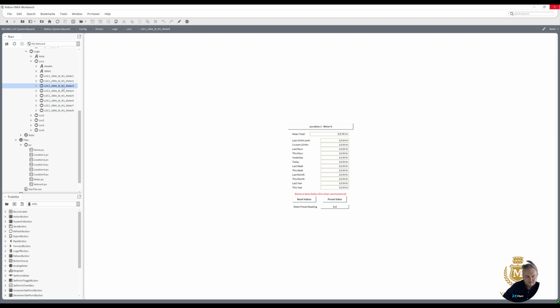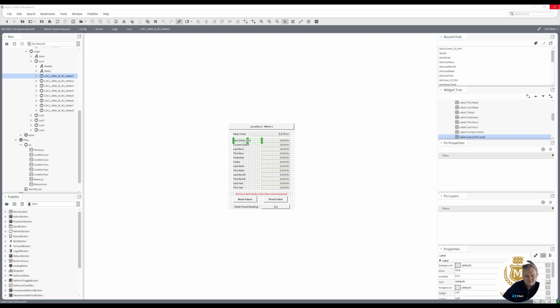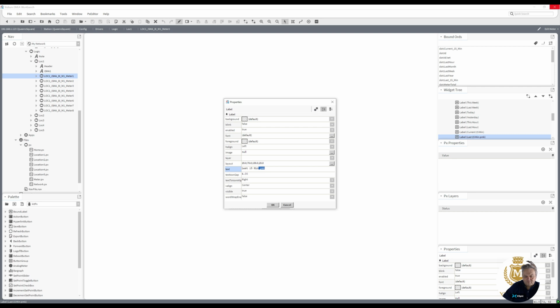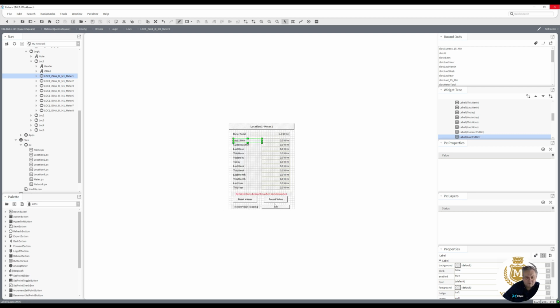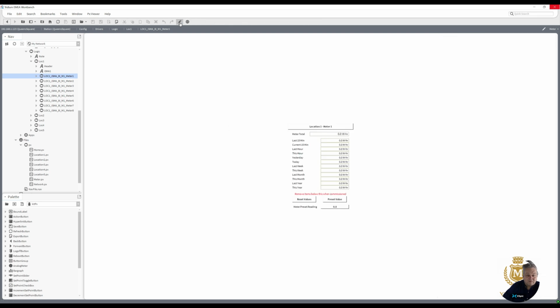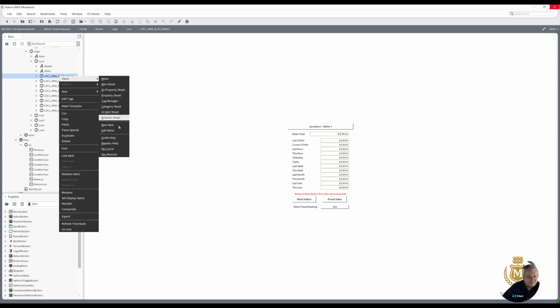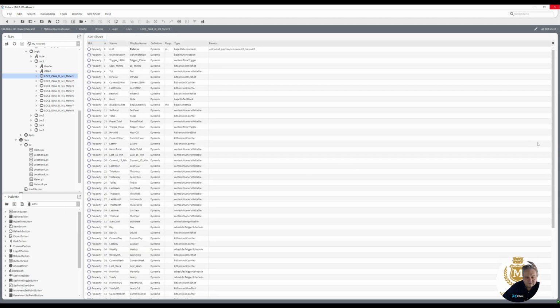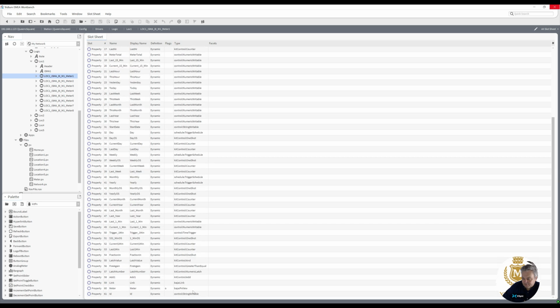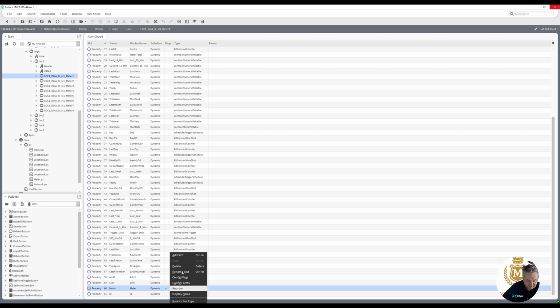Okay, it's the same graphic for all the meters, and I'll show you how I did that, because you do exactly the same for when you're doing fan coils. You won't make one graphic per fan coil. You will make one graphic for all the fan coils or all the fan coil types. So let's just right click that, views and AX slot sheet. Let's take out the view for that, which is this here. See this meter PX view? I'm just going to delete that.